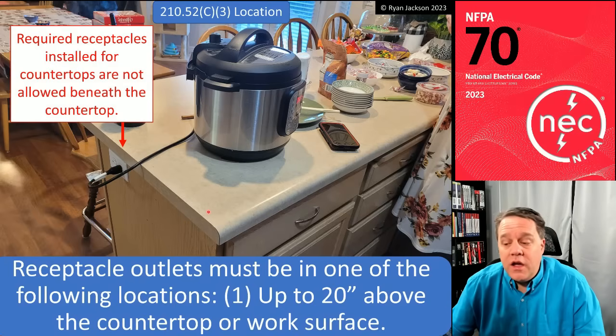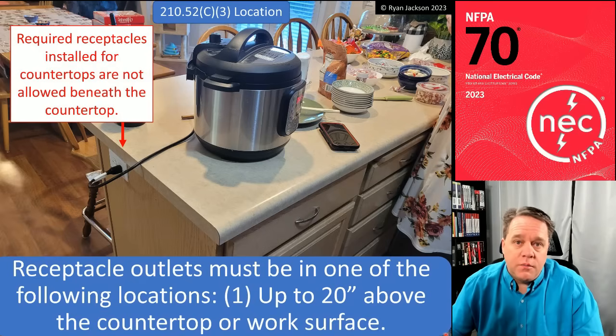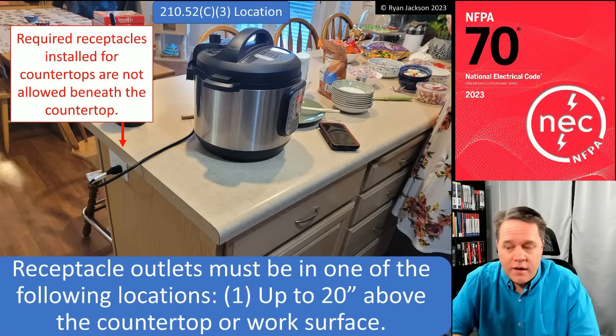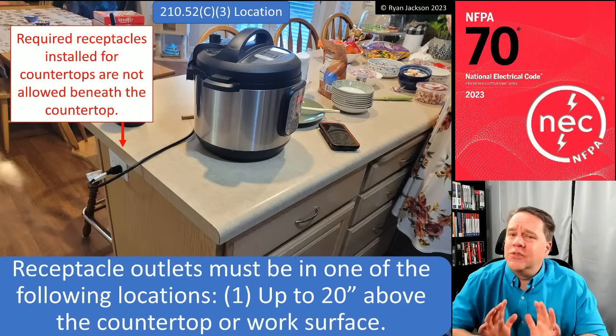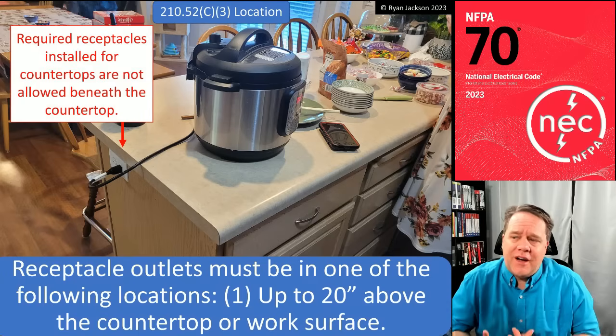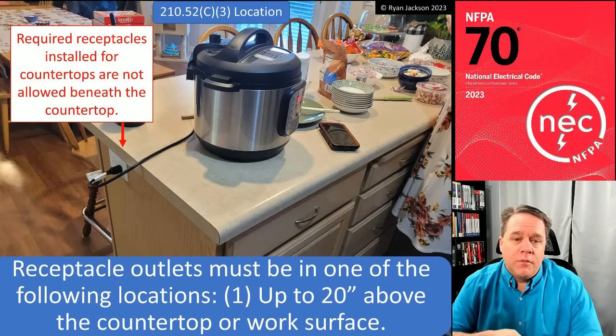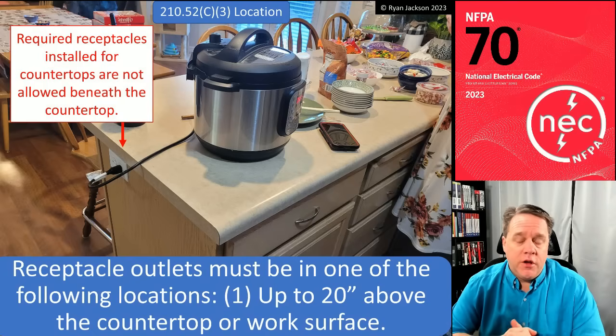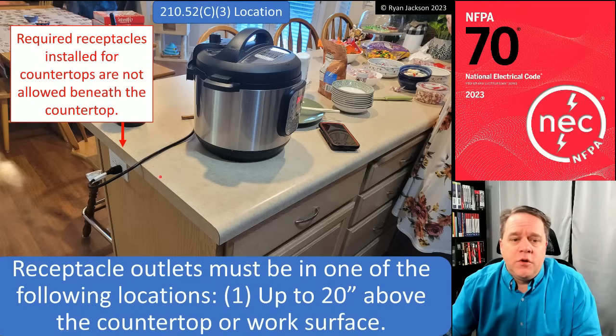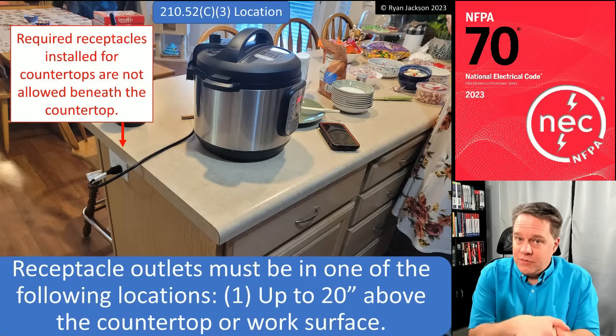If you're an inspector, you can't write someone up for an optional receptacle — it's not a required receptacle. But if you're an electrician, I'm going to tell you that putting a receptacle down there is a very bad idea. First, you'll probably have a fight with the inspector who may not read the code as closely as we have. More importantly, you don't want to be the cause of a horrific injury. I've acted as an expert witness in several court cases — I don't worry about getting sued all the time, but this is a more common injury than people think.